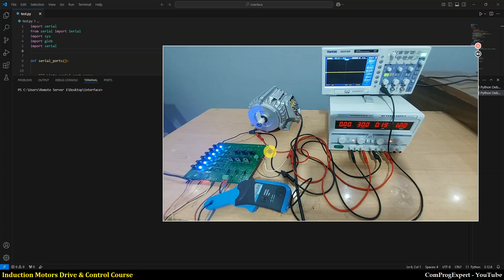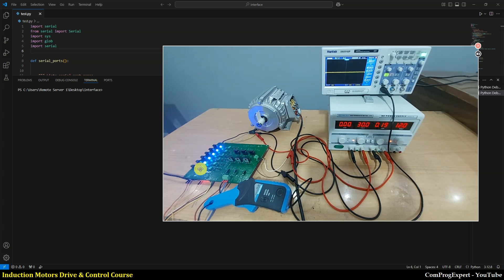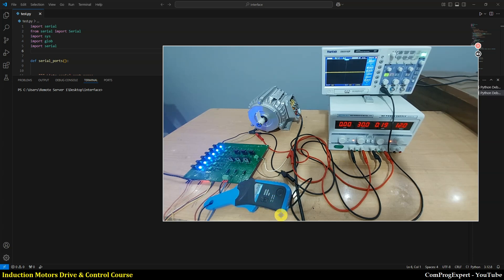The DC link of this inverter is 310 volts, and we will perform corresponding tests in the next videos. This is the DC link and here are gate drivers. I am going to measure the current using this current clamp for this phase of the motor.